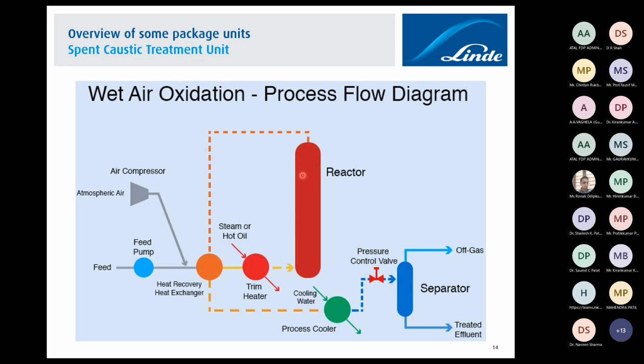And second, the gaseous product, or purified caustic that also comes along with the gas, is cooled with the help of a cooler and converted into liquid. You have a pressure regulating valve, so only liquid goes to the separator, and whatever gaseous component is escaping, you can release as off gas to the flare. Whatever is in liquid form, the treated spent caustic, we can now send to the wastewater treatment plant for further treatment, because ultimately it is a caustic, it is alkaline. So at the ETP, by acid dosing, it will be neutralized and mixed along with the other water pollutants or effluent coming from the refinery. So this is how the wet oxidation process works.